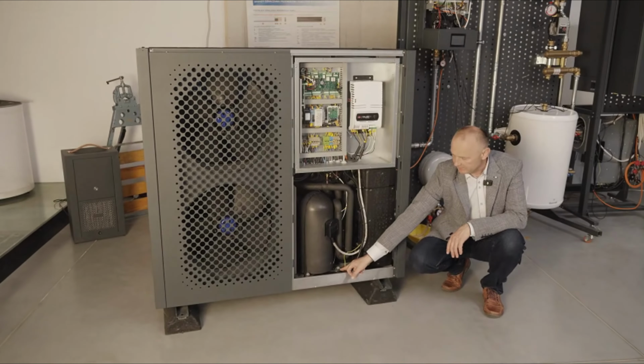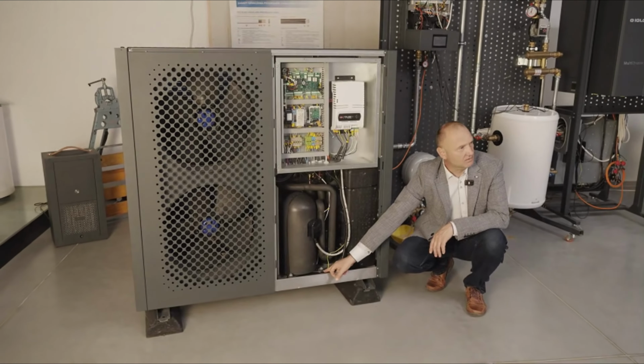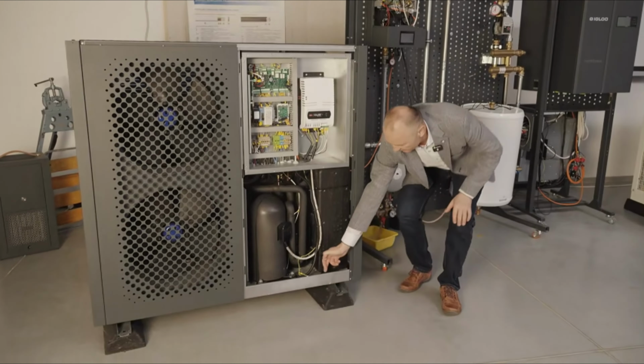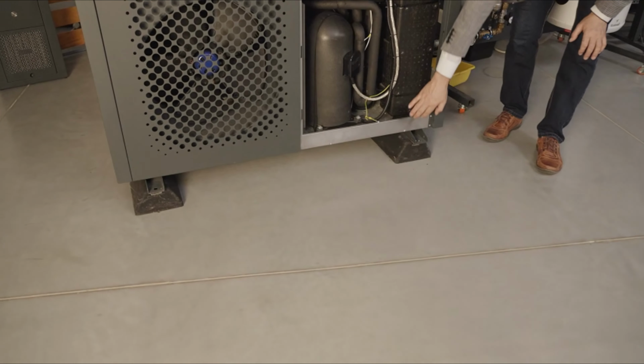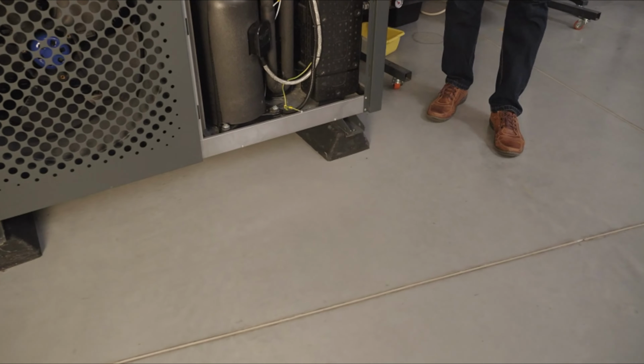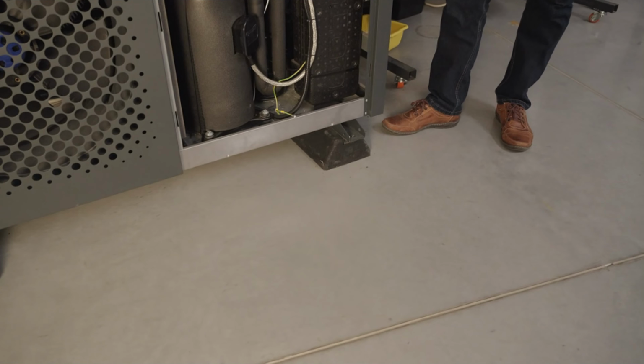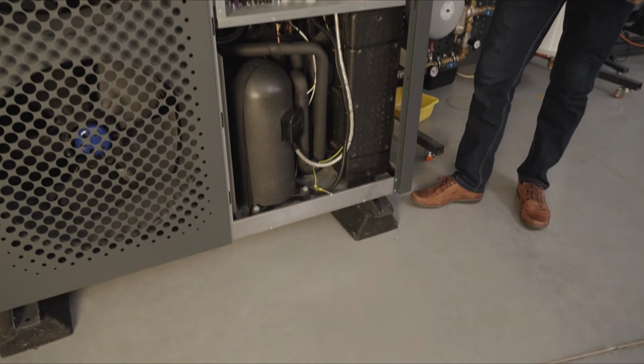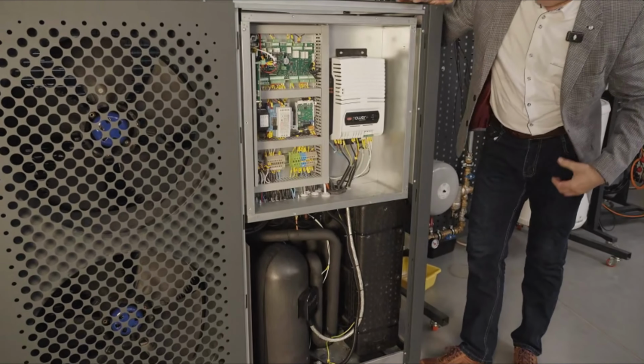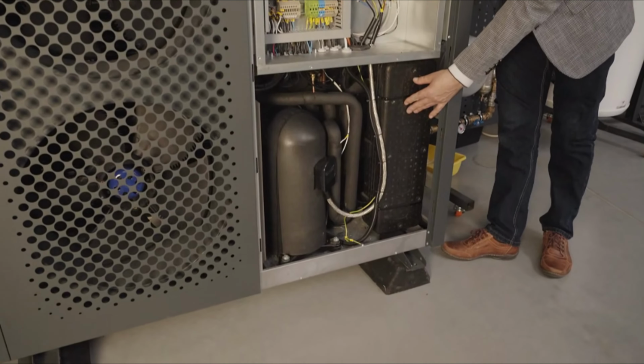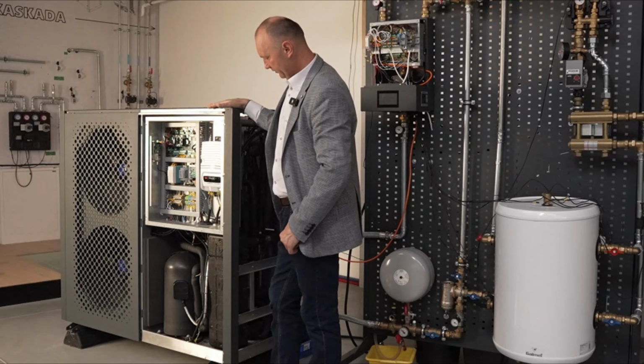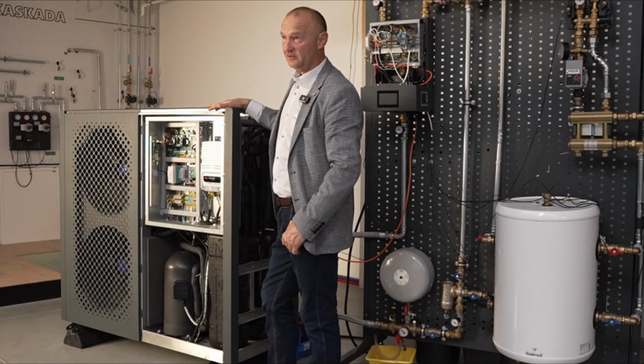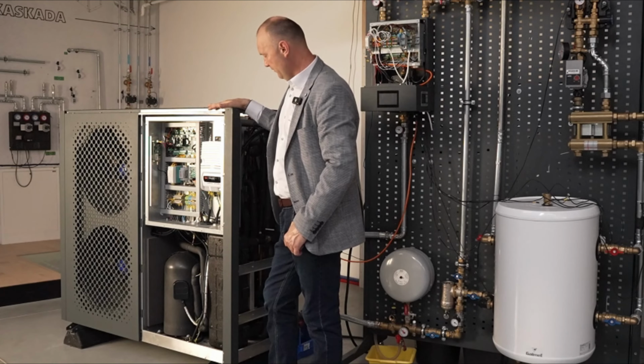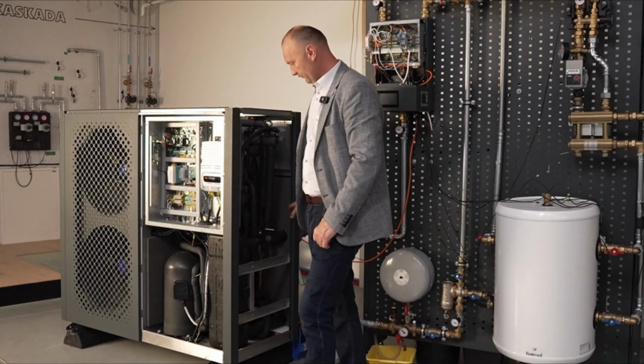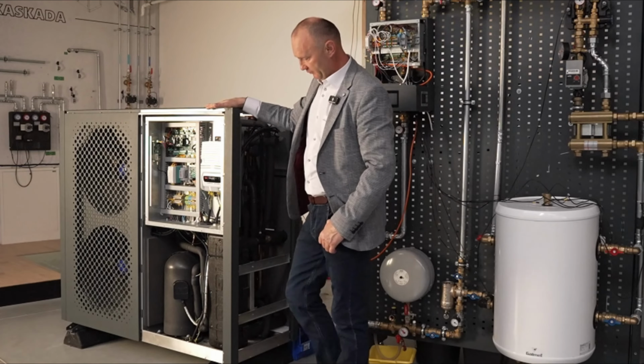The compressor is mounted on 4 vibration isolators to the base, which base is again mounted on further vibration isolators to the heat pump base. Consequently, we have a double vibration isolation system installed in this heat pump. The next important component here is the heat exchanger. Right here, underneath this protective cover, you'll find the heat exchanger. This is the condenser, which is where the compressor transfers the heat it generates. This heat is then subsequently transferred to the water that is being heated by the heat pump.